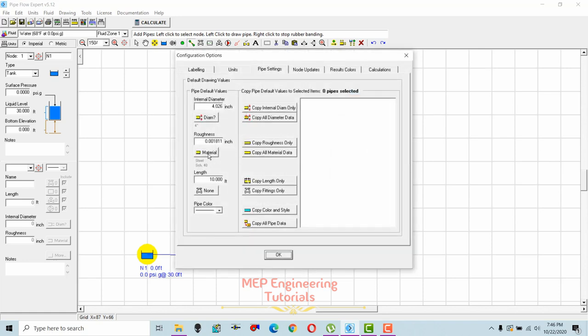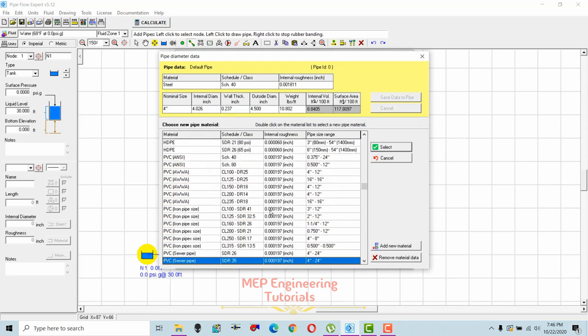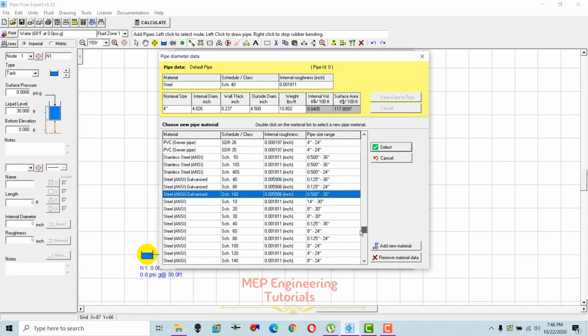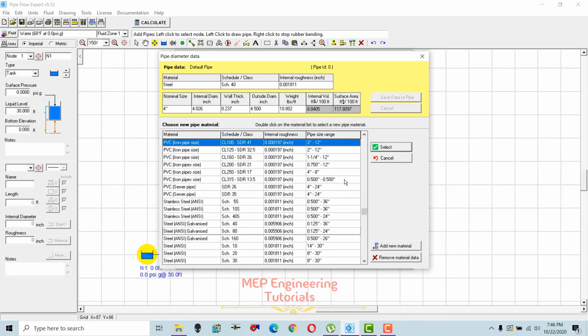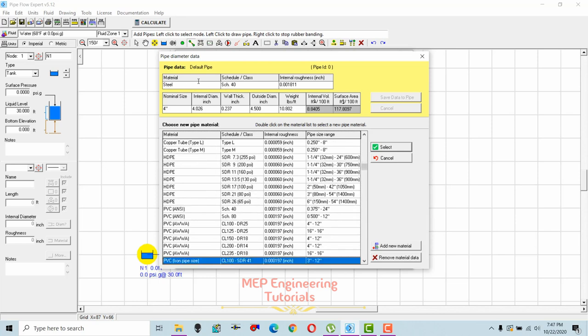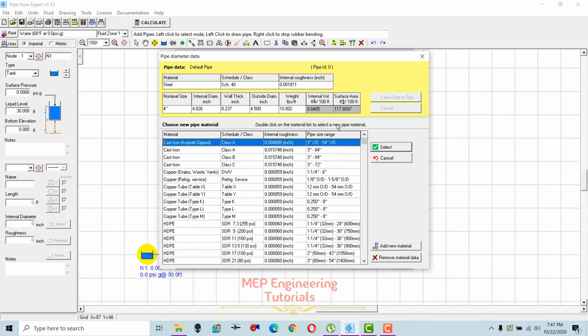In this dialog, you can change pipe material, diameter, and length. Going to the material dropdown, you can see all pipe materials are already in the software. One great feature is that all materials, fittings, and their K-values are built in and it calculates pump head automatically. For this example, I'll keep steel Schedule 40 and change the pipe size from 4 inches to 2.5 inches, depending on your pipe size calculation.